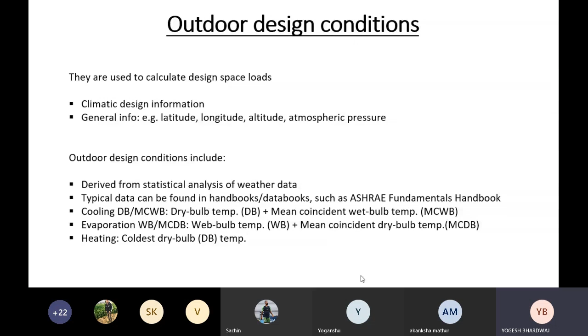So there we will take fixed values for dry bulb temperature and a mean coincident wet bulb temperature in case of cooling. In case of monsoon load, I will take the maximum wet bulb temperature and mean coincident dry bulb temperature. For heating load, I will take the coldest dry bulb temperature as ambient conditions while I evaluate the heat load. So these will be my ambient temperatures.